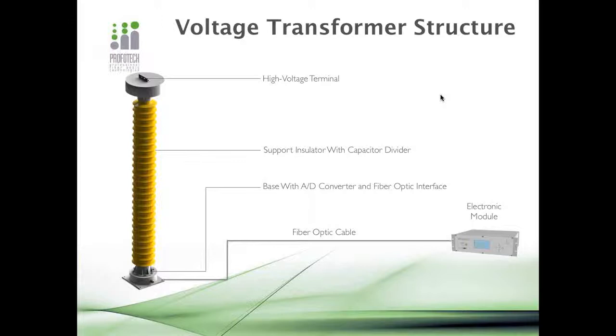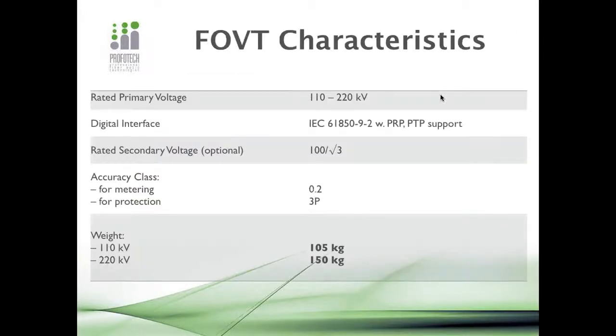So you can see the advantage, and this advantage is just like the advantage of the optical current sensor: no electromagnetic interference could influence the signal. So the signal is absolutely clear of any kind of oscillations and stuff from the outside. It's only the pure signal of current and voltage sensed by the sensor and nothing else. So it's completely precise, and it's almost impossible for the protection devices to catch some impulse and make some false trip. Nothing, just a pure signal.